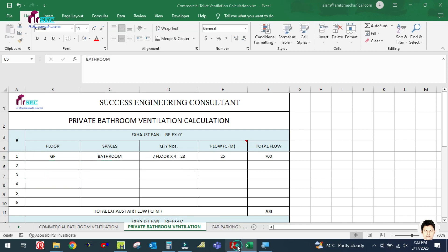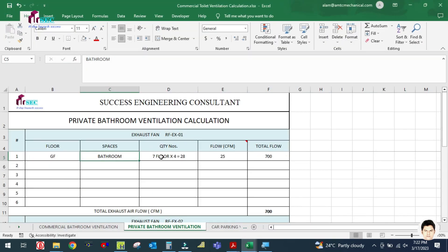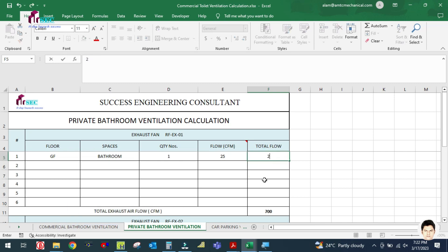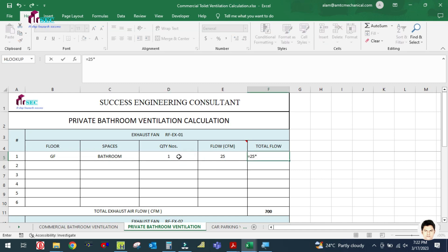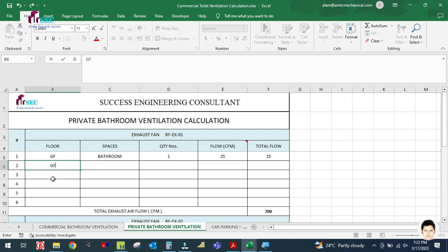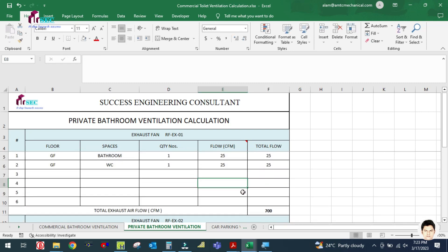The floor is ground floor. We are calculating for the bathroom space first — quantity is one, so total CFM is 25 into 1, which equals 25 CFM. Next is the ground floor WC — quantity is one, and for one WC we are considering 25 CFM, so we get 25 CFM.